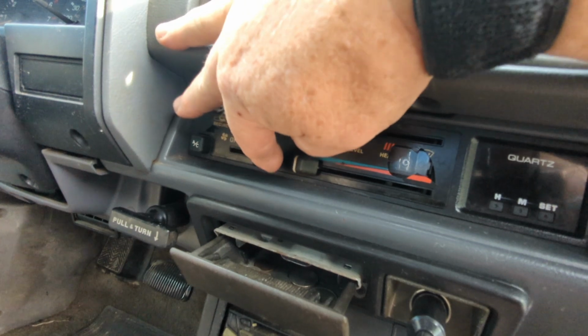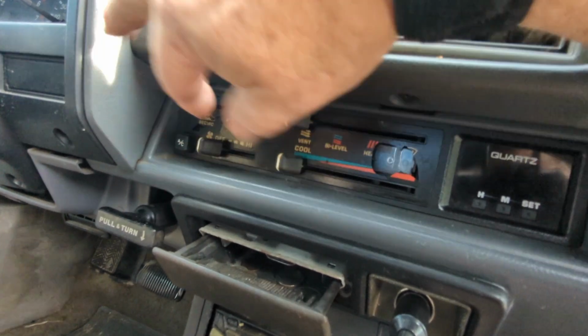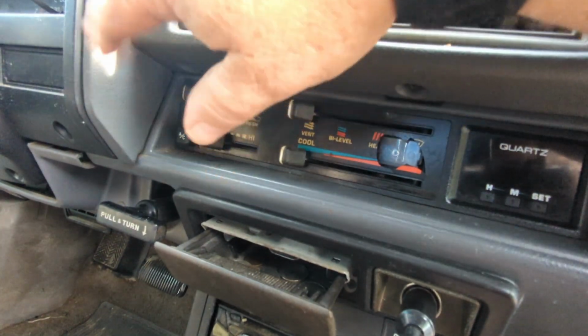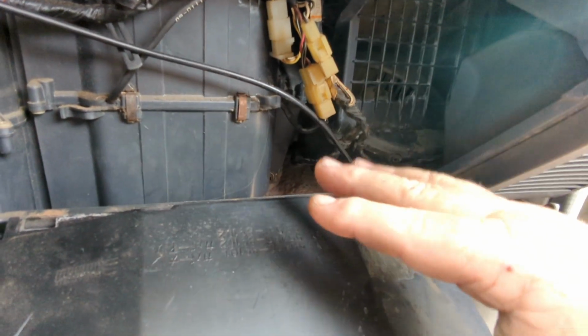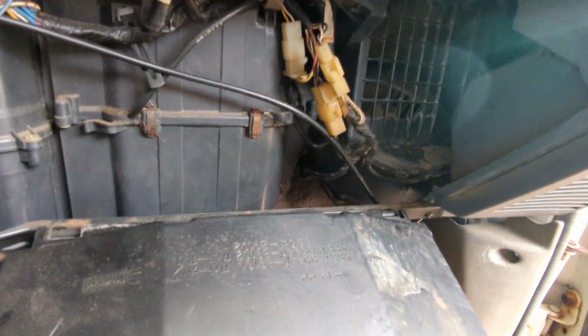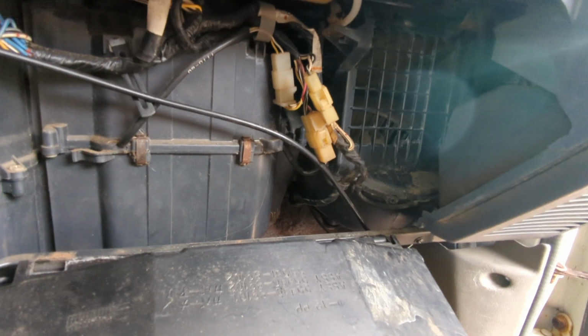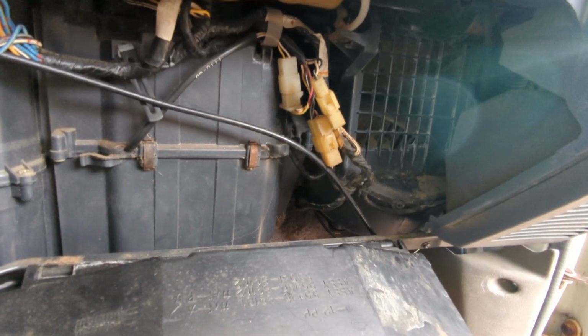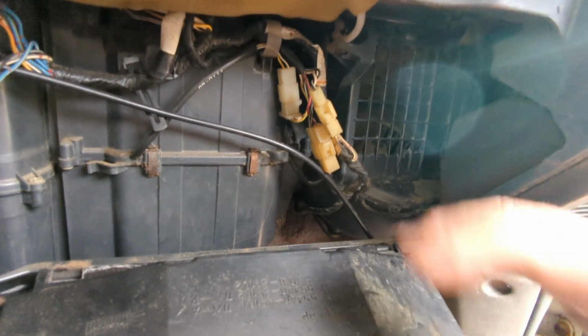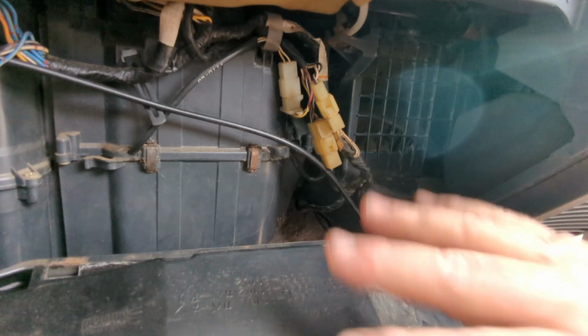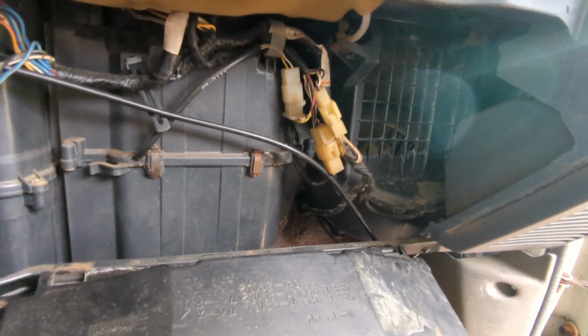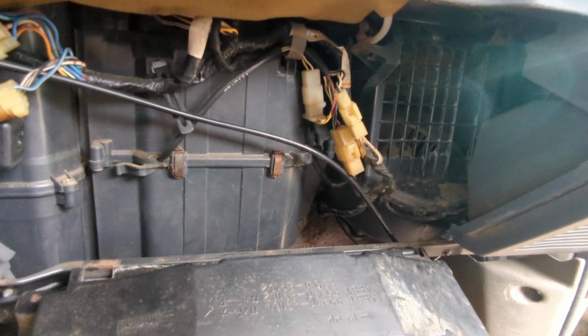Then of course here's your fan speeds. Sometimes these rheostat switches go bad, or there will be a resistor underneath here by the blower motor. The resistor can go bad, which changes the voltage output to the motor, hence changing the RPM. So you just want to first make sure all this is in pretty good shape and it's all working, all the controls working correctly.